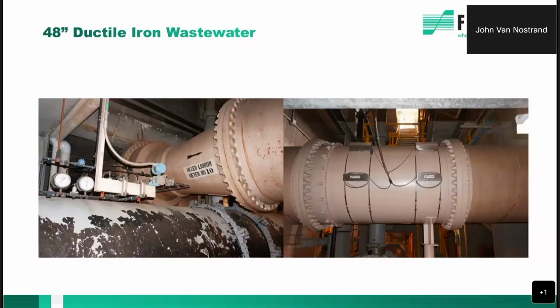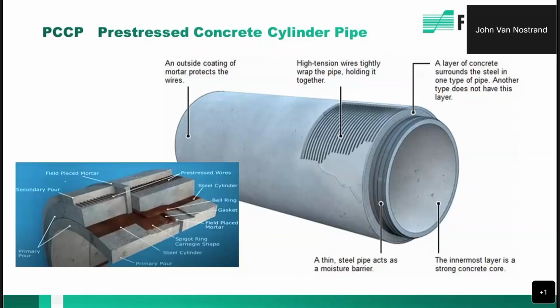This is an actual Venturi meter, but it's in a wastewater stream. You don't necessarily see that very often. It's a mixed liquor application, but needless to say, the impulse lines were plugging on this transmitter. So FLEXIM offered a very easy transition to install a meter, and they just abandoned that Venturi altogether, using the power from that DP transmitter to our meter and using the same signal wire. Again, we were in and out of there in no time, and the customer is extremely happy.